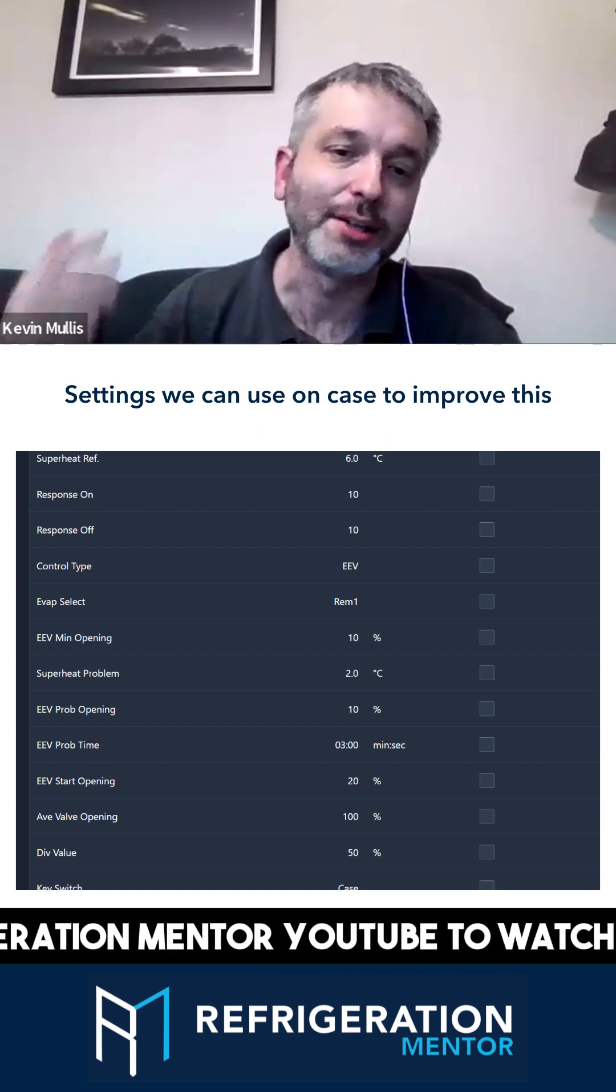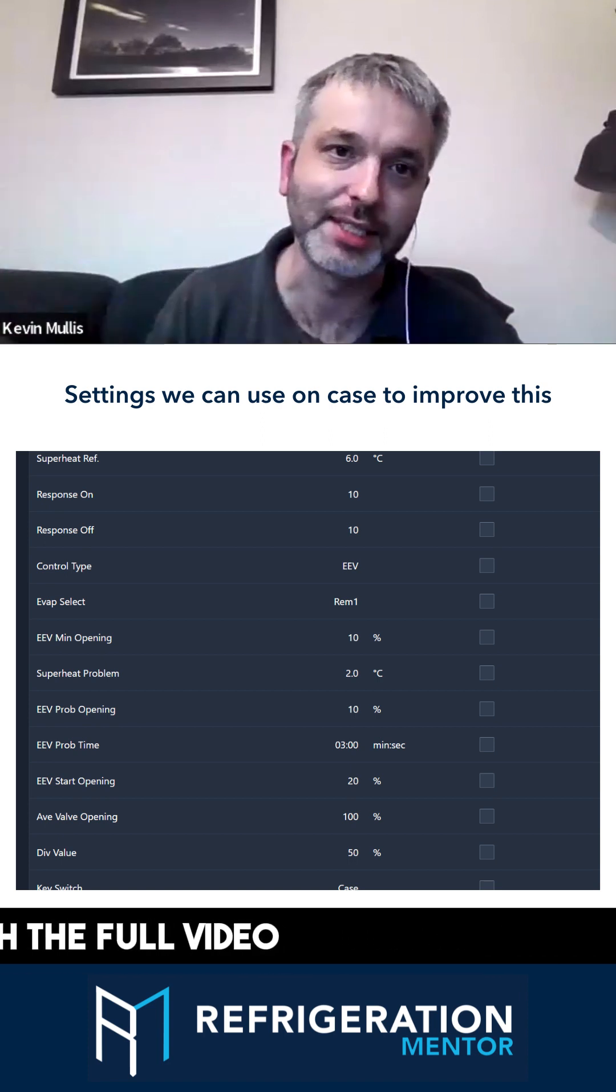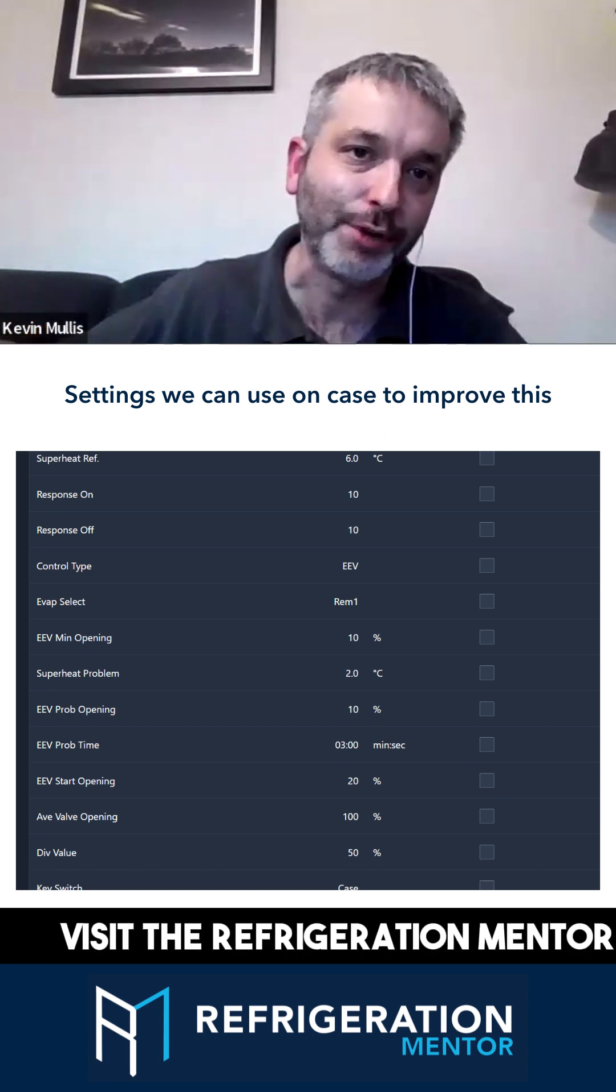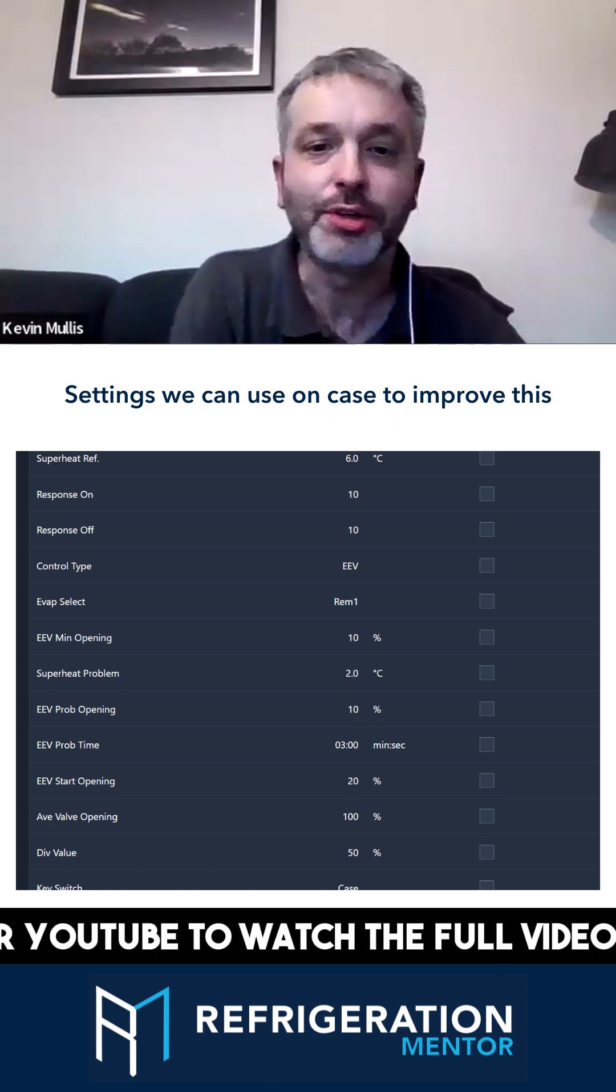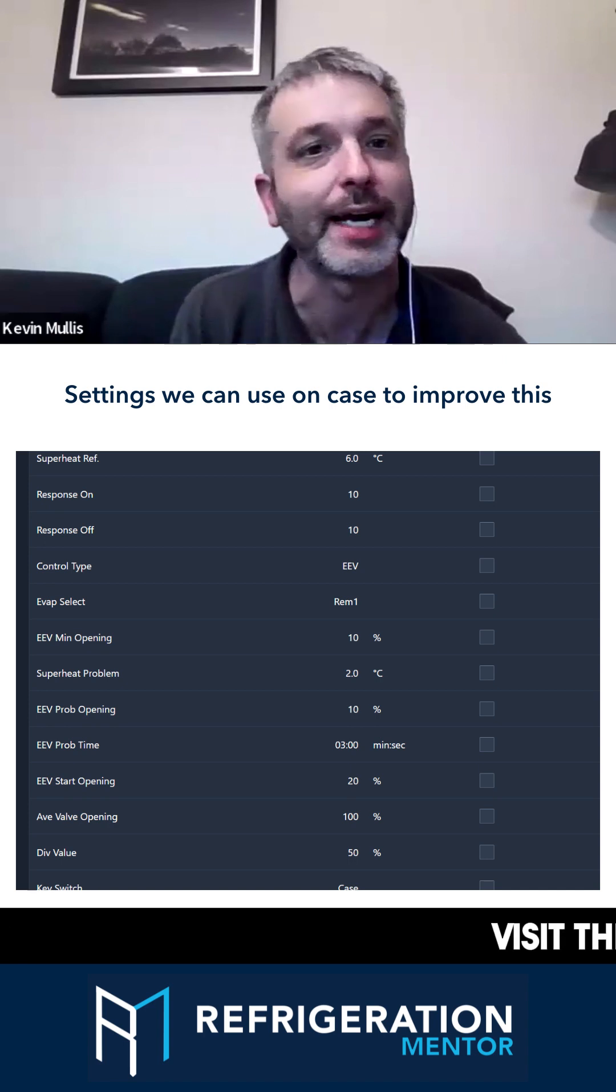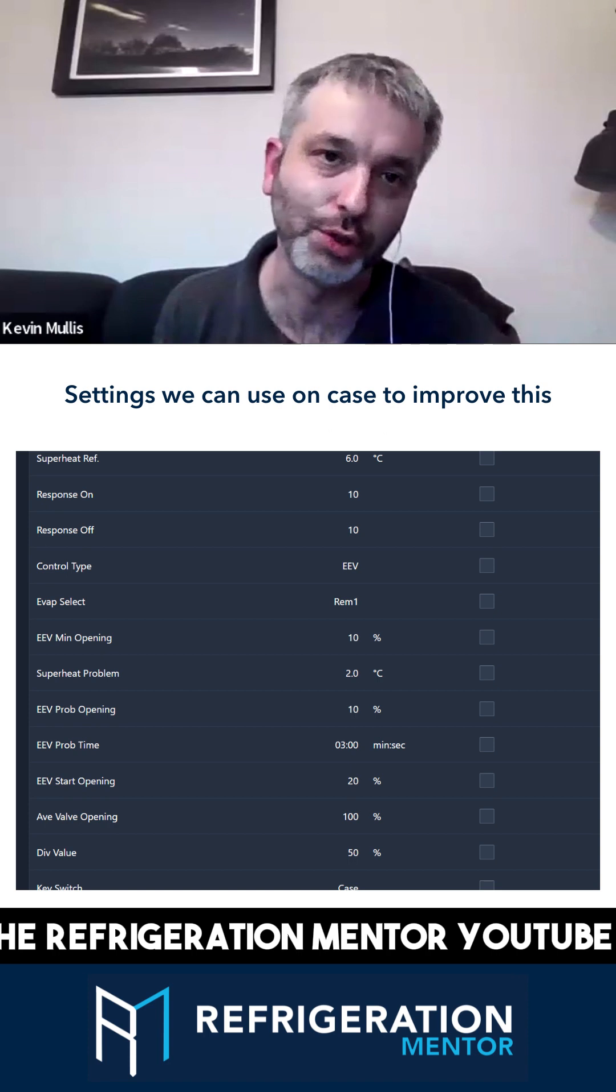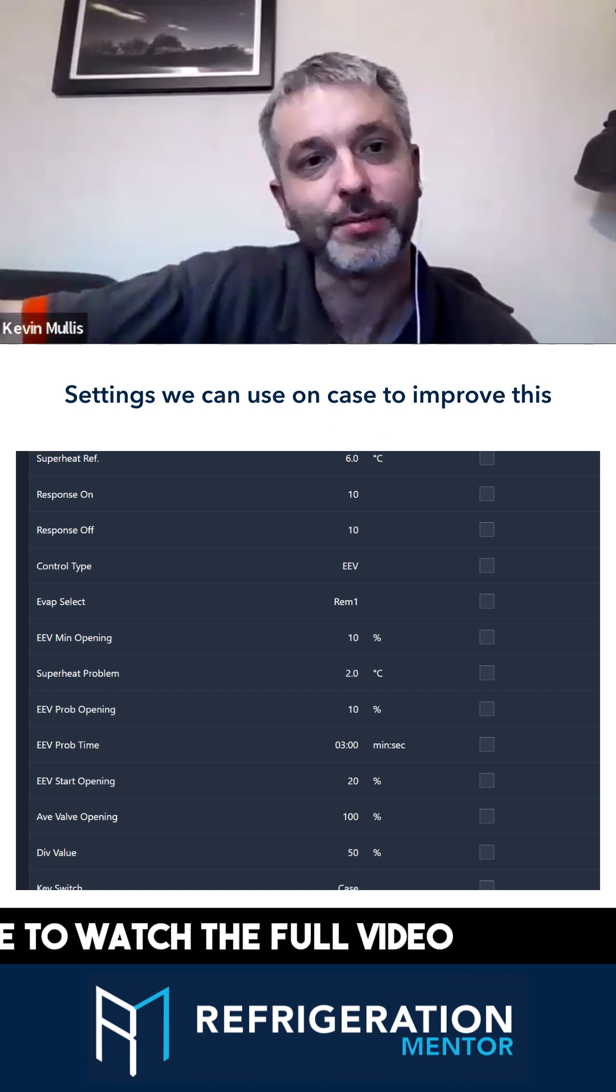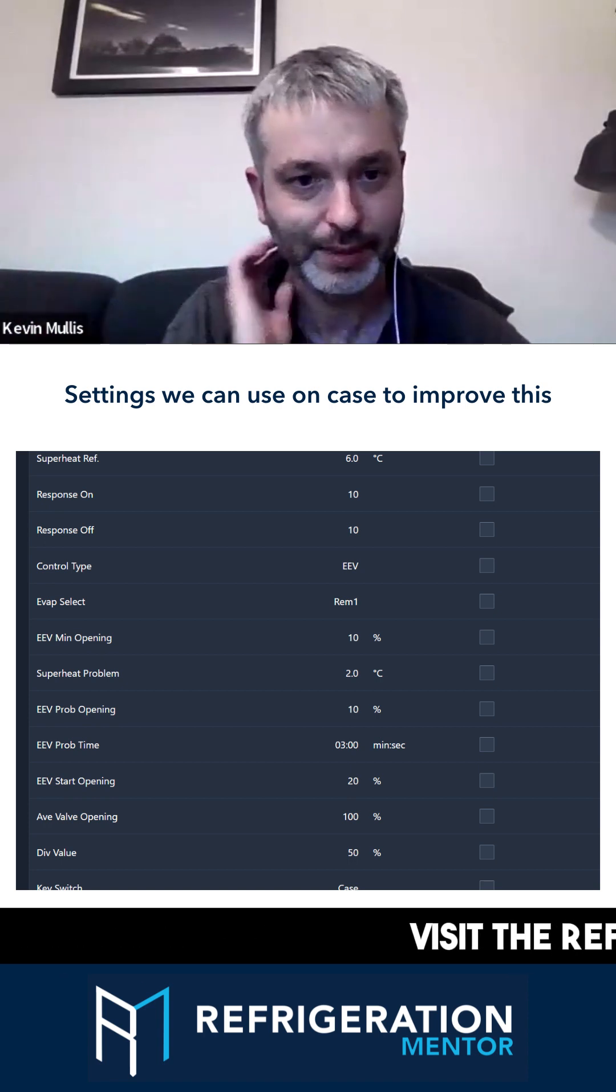The transducer doesn't need things like start opening and probe opening to keep a flow in the system. Start opening gives you the opportunity to get liquid to your probe if you're running on a probe for inlet temperature rather than a transducer. You can set that to 10% with a transducer because it will see the true superheat from the get-go. If you've got an inlet probe as your only source of evaporating temperature, especially if it's a long way away from the inlet, you need that number to be a little bit higher to get some liquid to it.